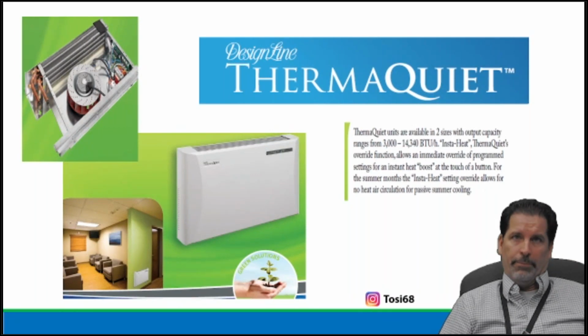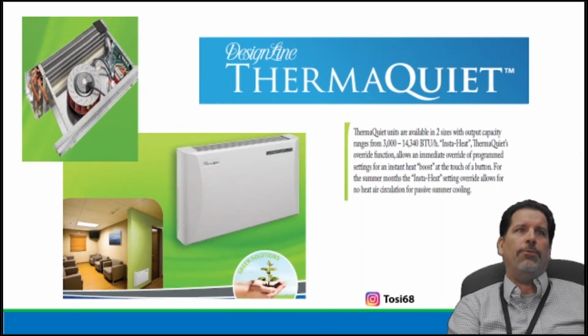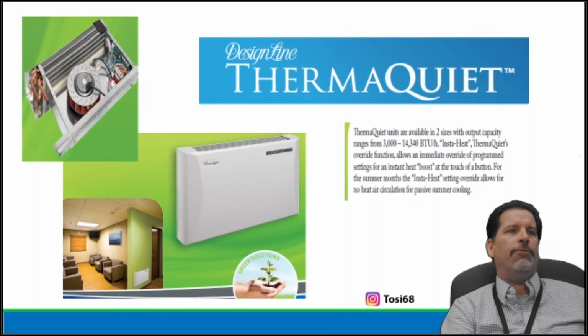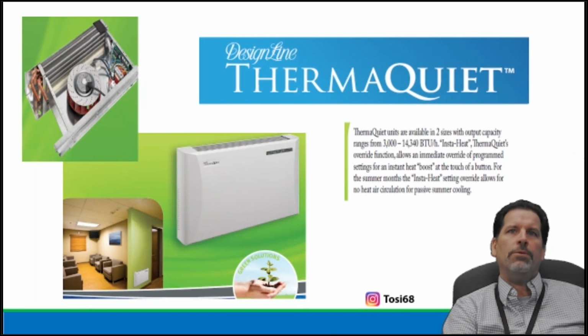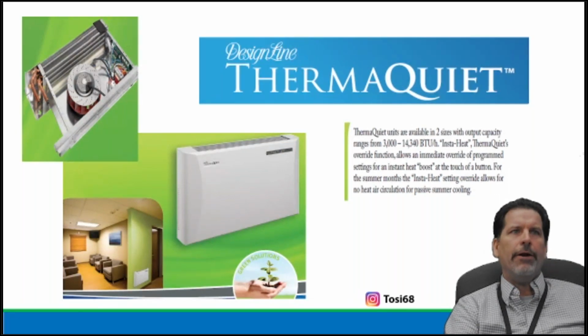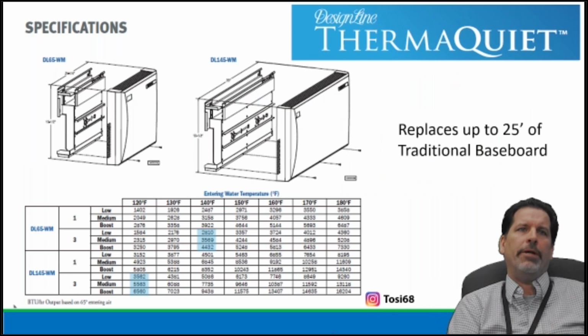So they have the ability to deliver 3,000 to almost 14,400 BTUs, or 14,300 BTUs. This is pretty wild. It's a hydro coil, meaning it has a modulating fan, air circulation, a boost feature. Some of the specifications: 140 on the smaller model, we're delivering almost 3,600 BTUs with 140 degree water.